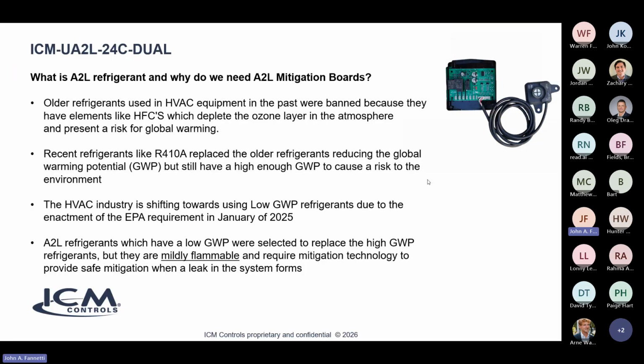So first of all, we like to start out by what is A2L refrigerant? Why do we really need A2L mitigation boards? Typically, older refrigerants used in HVAC equipment in the past have HFCs in them, refrigerants that are not good for the ozone layer, and so they present a risk to the global warming of the planet. So recent refrigerants replaced those old refrigerants. Things like 410A that had a high global warming potential are now being replaced.